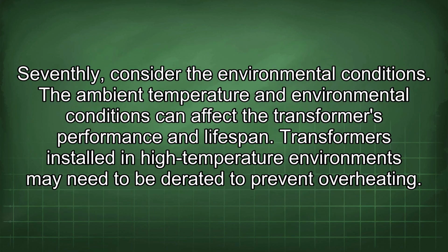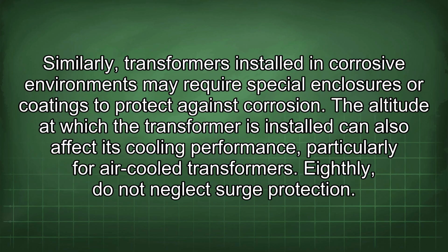Seventhly, consider the environmental conditions. The ambient temperature and environmental conditions can affect the transformer's performance and lifespan. Transformers installed in high-temperature environments may need to be derated to prevent overheating. Similarly, transformers installed in corrosive environments may require special enclosures or coatings to protect against corrosion. The altitude at which the transformer is installed can also affect its cooling performance, particularly for air-cooled transformers.